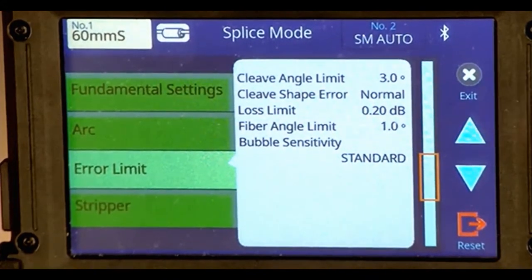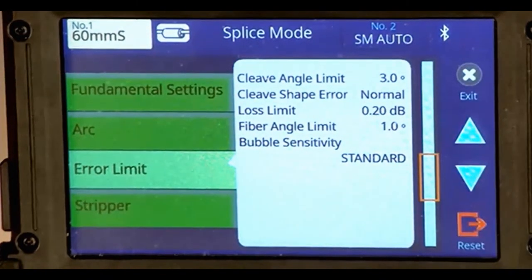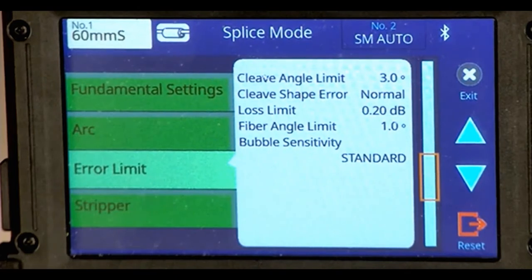This is showing the fiber angle limit. That's the angular misalignment that it will tolerate before you get an alarm. 1 degree is very generous. To be honest with you, if you're keeping those blue ceramic alignment V-grooves clean and there's no dust or coating debris in there, usually the fiber angle is going to be 0.1, 0.0, 0.2. If you start seeing 0.3, 0.4, then I'm going to want to look at those V-grooves and see if there's some dust in there. Here it's saying the bubble sensitivity is standard.